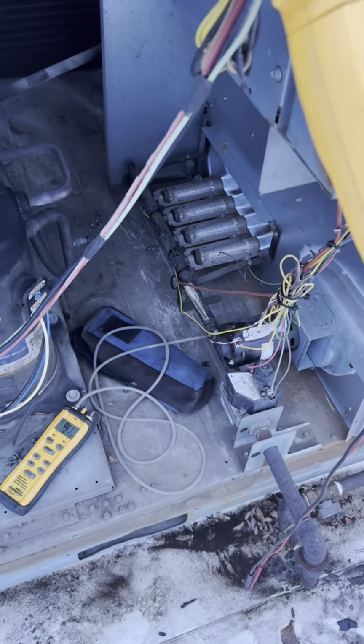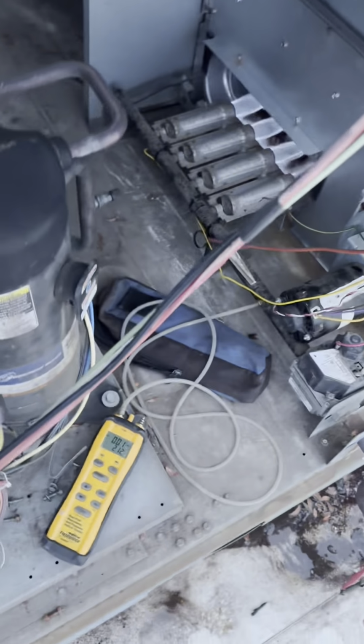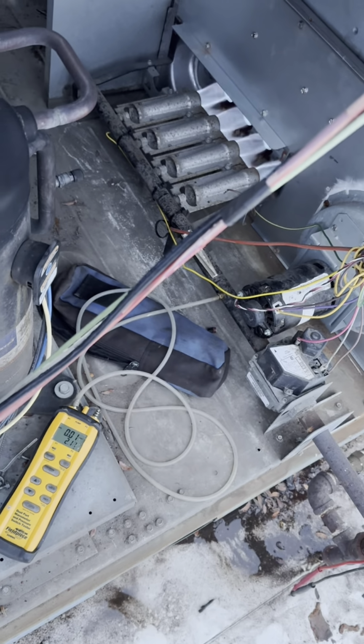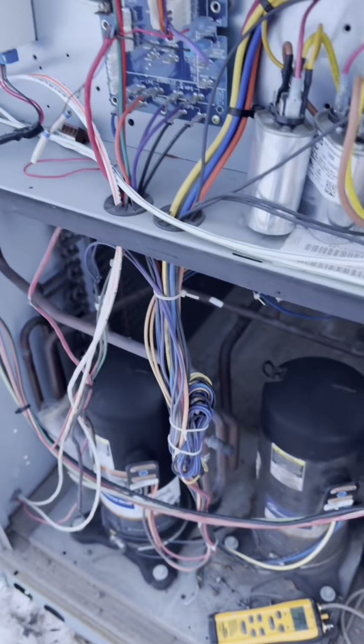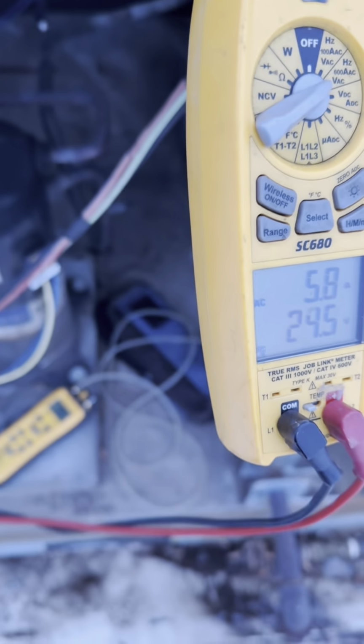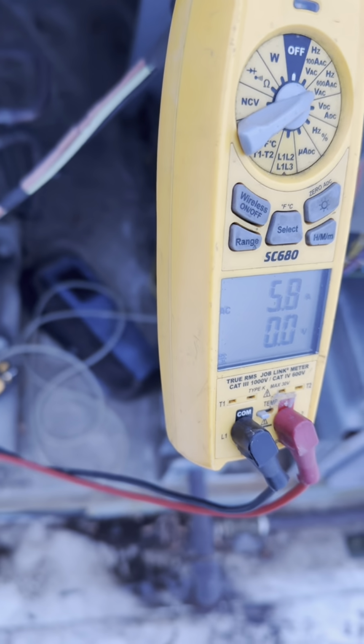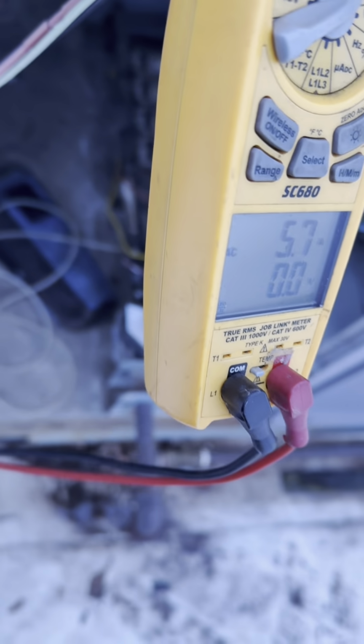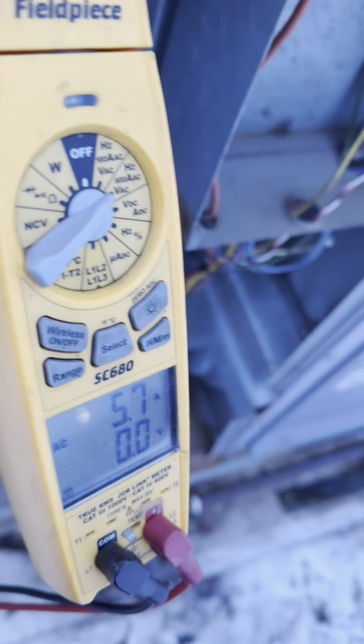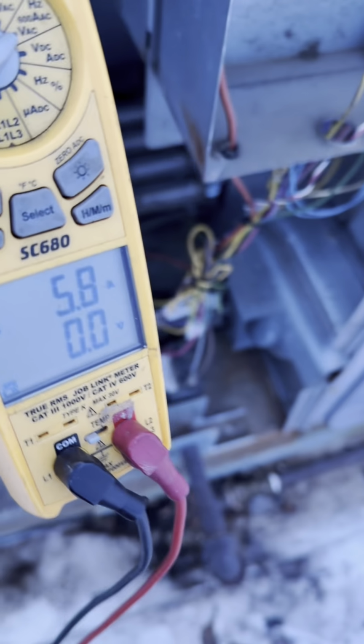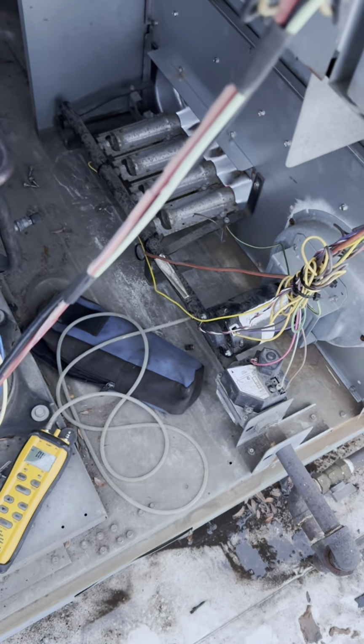All right, we're back on. Nice blue flame. Right now we're only calling for W1, and we can verify that: 24 volts W1 to common, and W2 to common, 0. So we're only calling for W1, so we're on low fire.